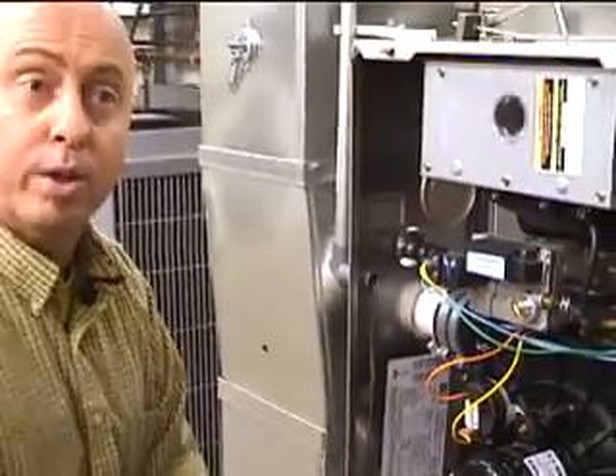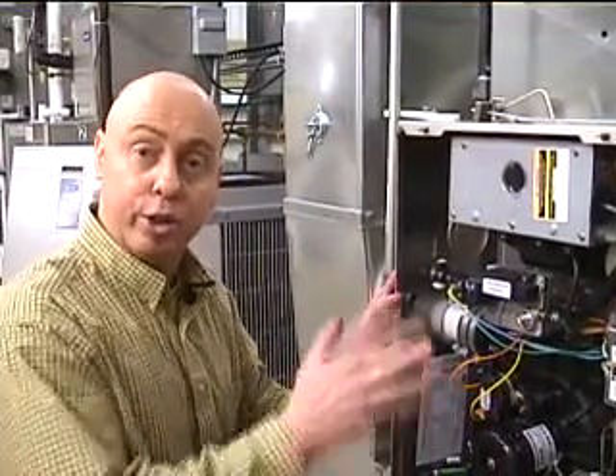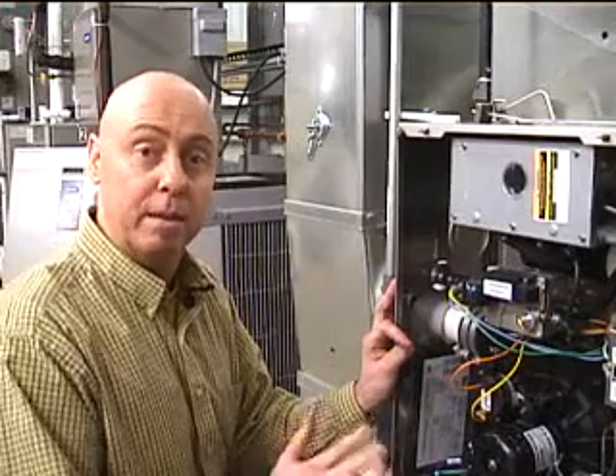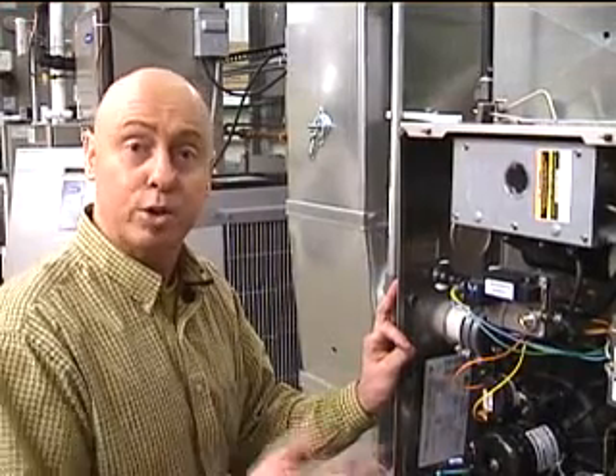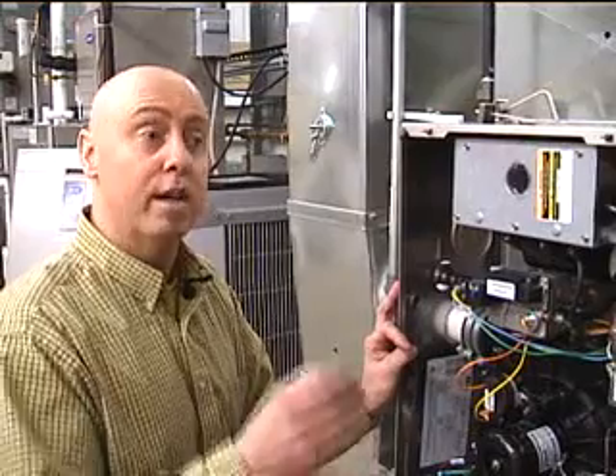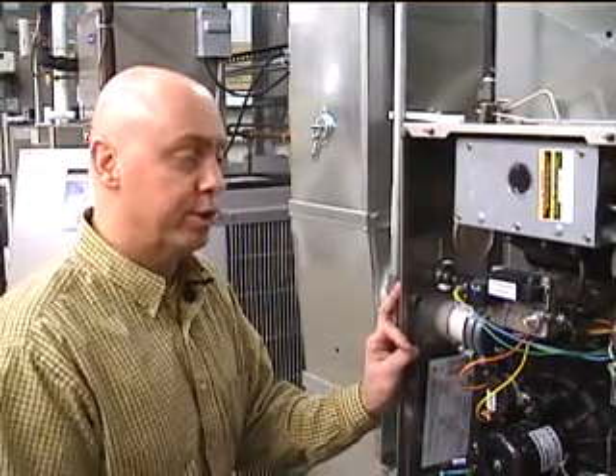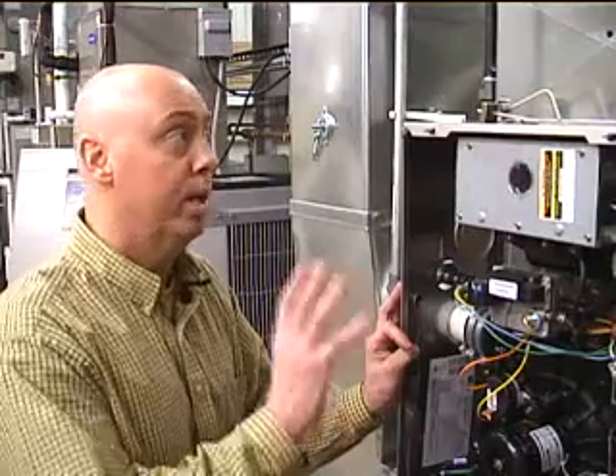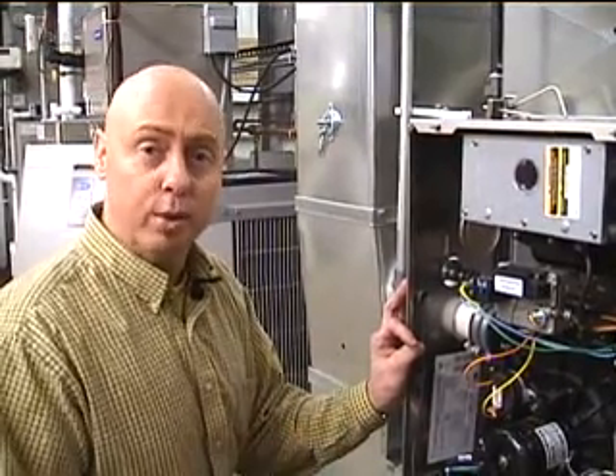Typically residentially, we're dealing with 0.5 inches of water column as a maximum level. That is typically in the cooling mode. In the heating mode, furnaces are rated without an air conditioning coil because there's no guarantee that the furnace has air conditioning. It could be one without an A coil. So furnaces by themselves are typically rated much lower for airflow. So in the heating mode, they might be rated at 0.15, 0.25 inches of water column, which is considerably less than the maximal level. So if you're in the heating mode, checking your total external static pressure, you always want to stay under what the maximum level is, because if you're at the maximum when you're in the heating mode, when you go to air conditioning mode, you're certainly going to exceed that. And at that point, the airflow is going to be compromised considerably.